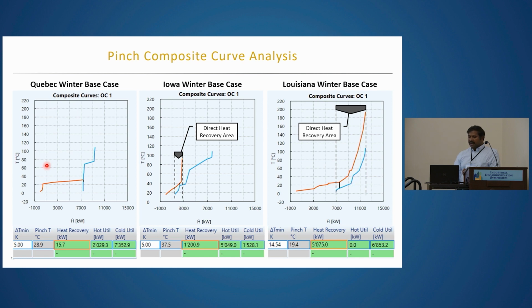So pinch analysis helps us identify whether you really need a heat pump, a combination of direct heat recovery and a heat pump, or no heat pump at all — there's simply no requirement for one in that particular facility. That's how we educate customers about this pinch methodology. Before they even go for a heat pump implementation, it's quite important to do this pinch analysis and then implement the heat pump technology in the facility.